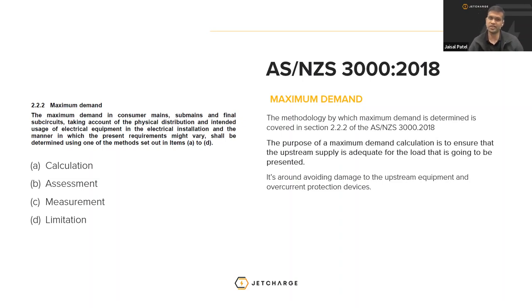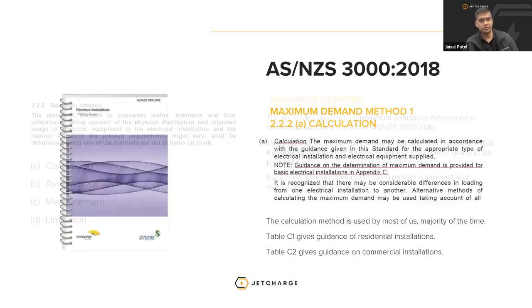The methodology that we're gonna typically use in this case is called calculation. Now, the reason why we do a maximum demand calc is obviously to ensure that the upstream supply is adequate for the load that is going to be presented. And it's also to avoid damage to the upstream equipment and overcurrent protection devices. Next slide.